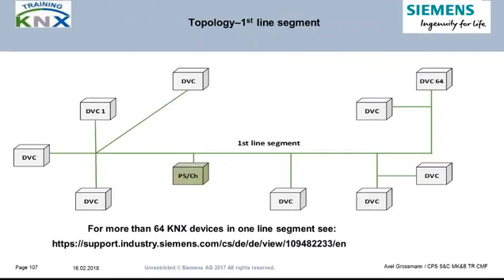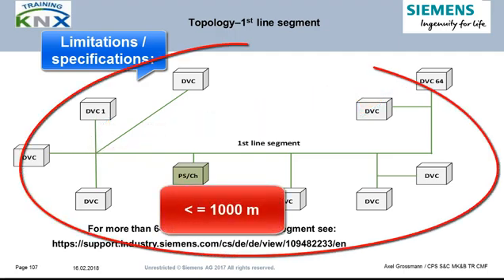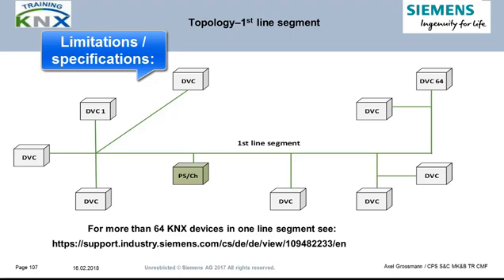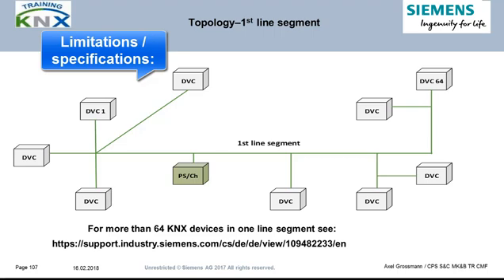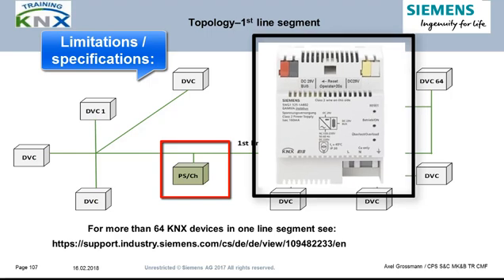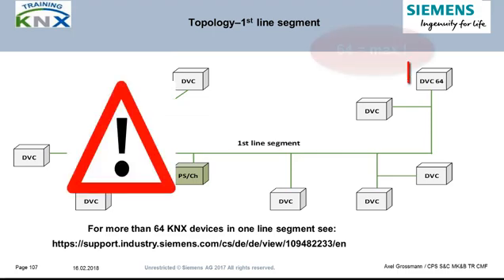Now let's have a look at the smallest unit in the topology of KNX: the line segment. The wiring limitations apply as learned in the chapter KNX installations. As for the devices, the maximum number of subscribers or bus devices must not exceed 64, including all connected couplers. Each line segment must also be individually powered by means of a specific KNX bus power supply unit with integrated choke, shown in green. Please bear in mind that the given limit of devices per segment cannot always be reached, since the power consumption of them may exceed the capacity of the supply unit.